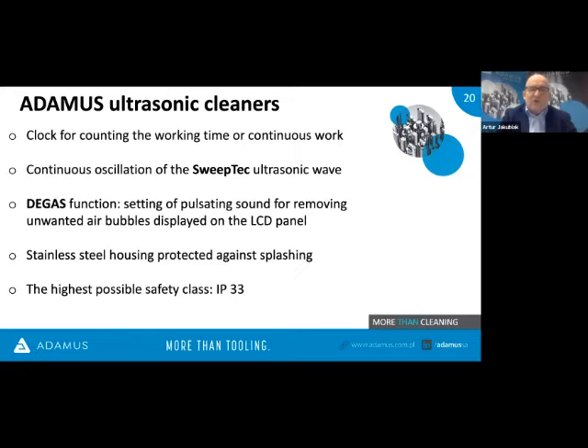So then, of course, we have a clock for counting the working time or continuous work. We have a continuous oscillation of the SweepTec ultrasonic wave. We have a degas function for removing unwanted air bubbles, which is a setting of pulsating sound displayed on the LCD panel, because generally we need to remove, before the cleaning, all the gases which are soluble in the water, just to make this cleaning process more effective. So we need only these air bubbles which we are creating with the ultrasound with the transducer. Then, of course, stainless steel housing.